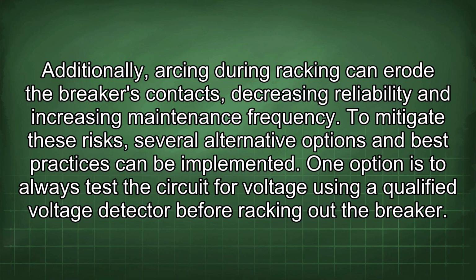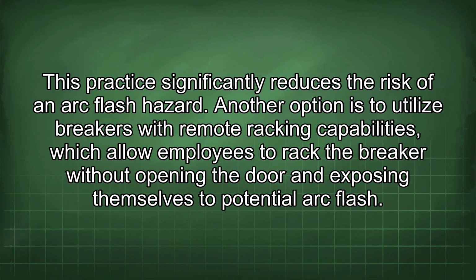To mitigate these risks, several alternative options and best practices can be implemented. One option is to always test the circuit for voltage using a qualified voltage detector before racking out the breaker. This practice significantly reduces the risk of an arc flash hazard. Another option is to utilize breakers with remote racking capabilities, which allow employees to rack the breaker without opening the door and exposing themselves to potential arc flash.